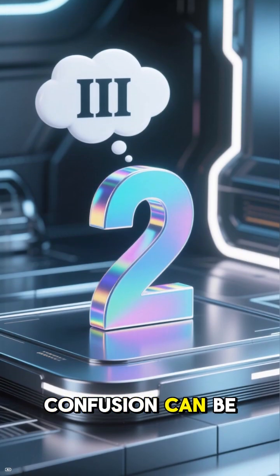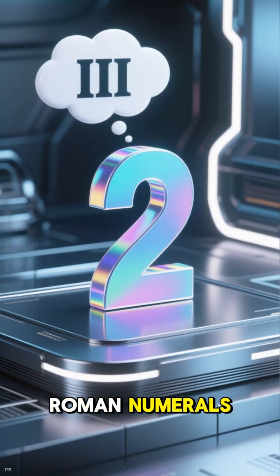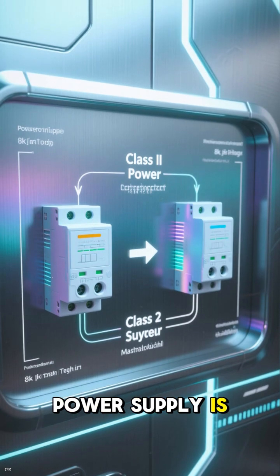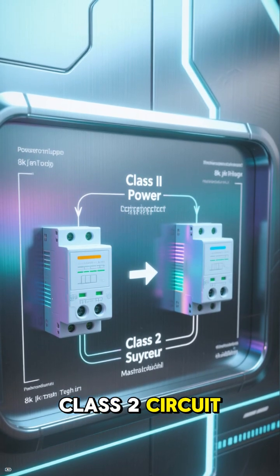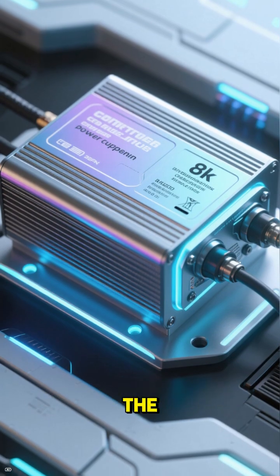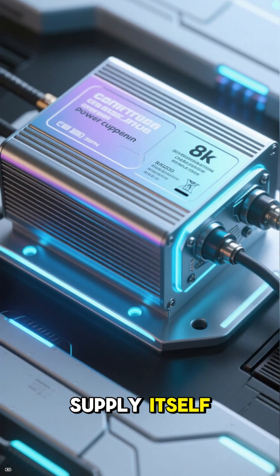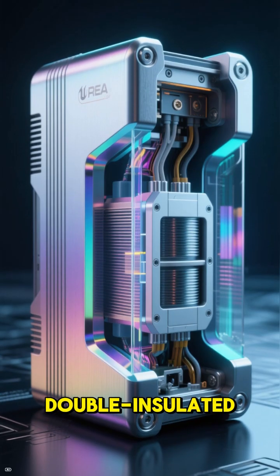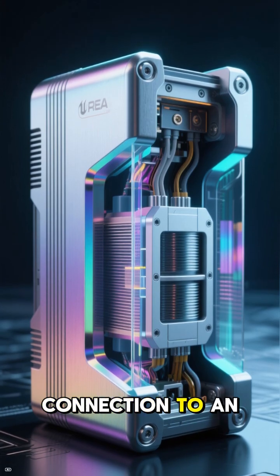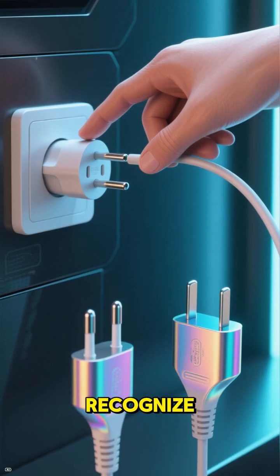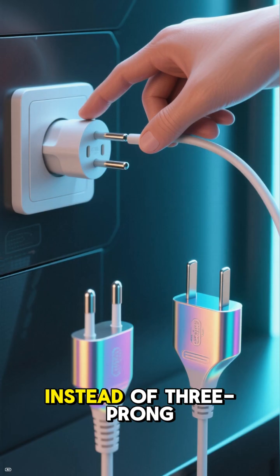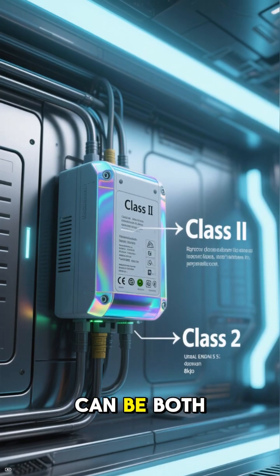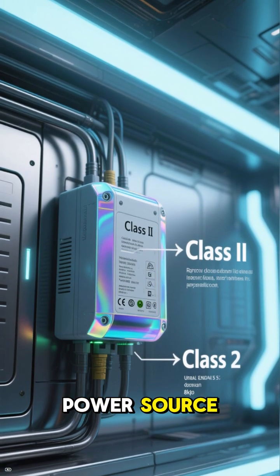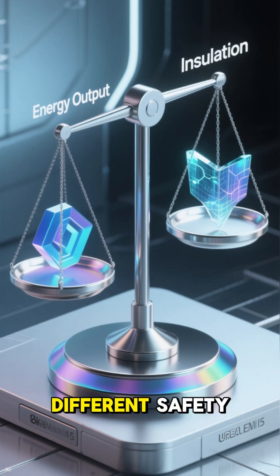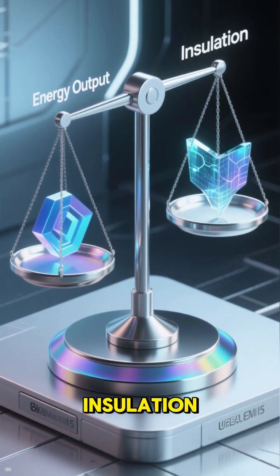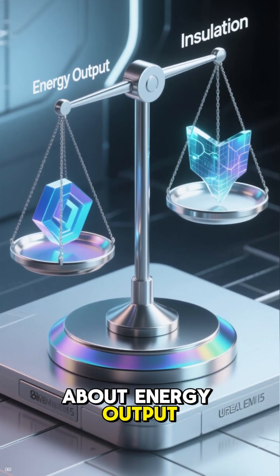Another point of confusion can be the term Class II with Roman numerals. A Class II power supply is not the same as a Class 2 circuit. The Class II designation refers to the construction of the power supply itself. It means the device is double insulated, so it doesn't require a safety connection to an equipment ground. You can often recognize these by their 2-prong plugs instead of 3-prong. A power supply can be both a Class II device and a Class 2 power source, but the terms refer to completely different safety standards. One is about insulation, the other is about energy output.